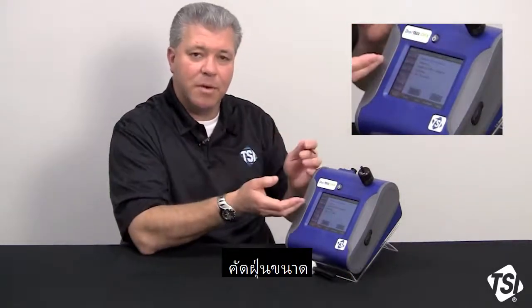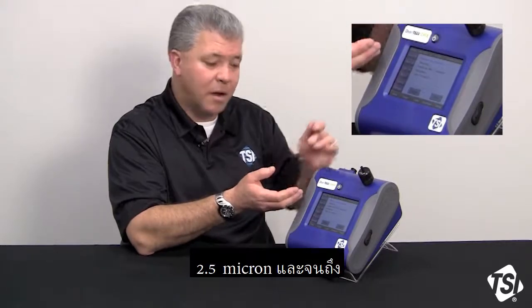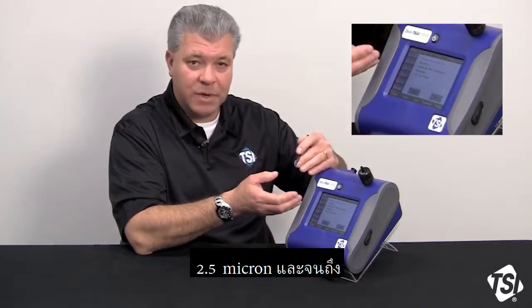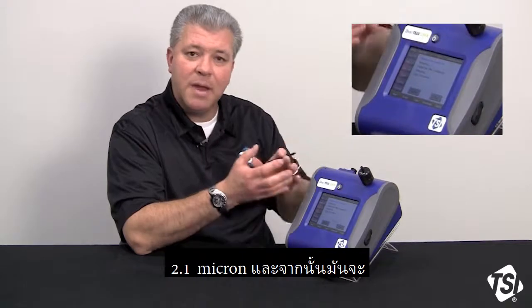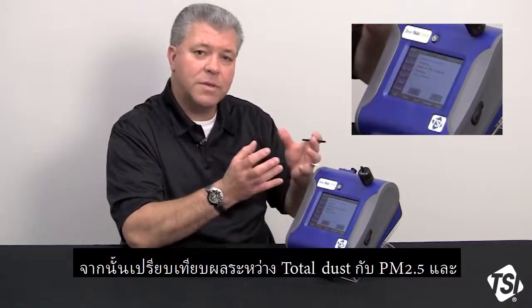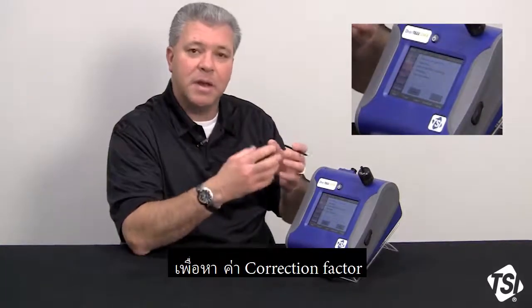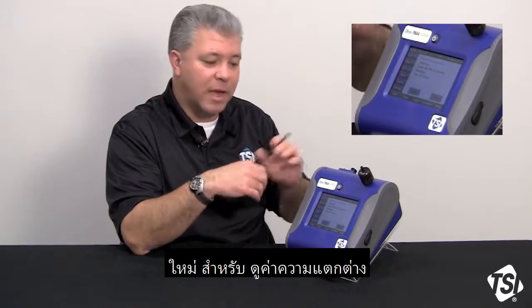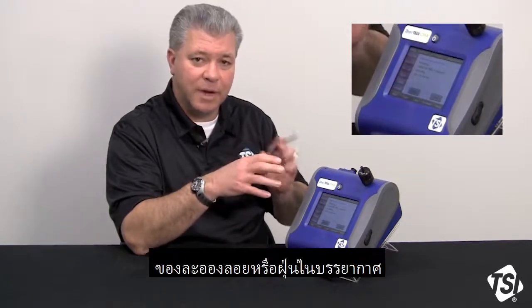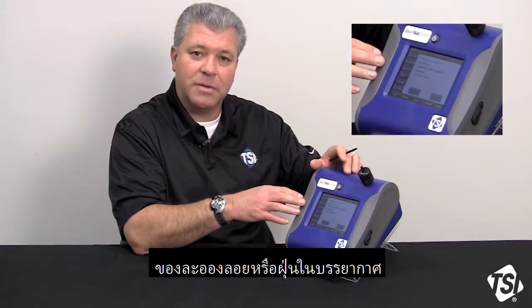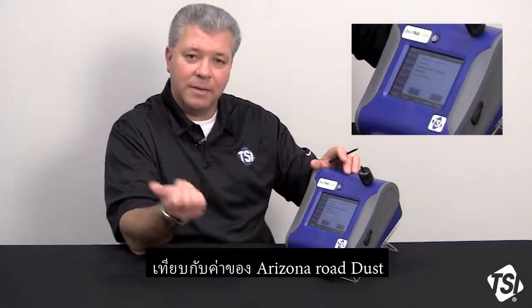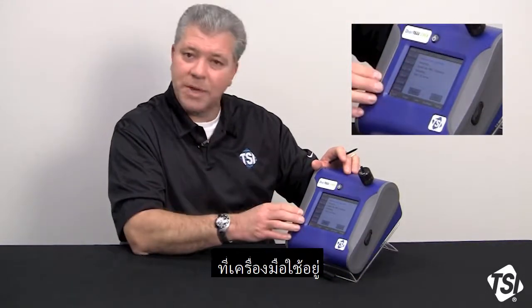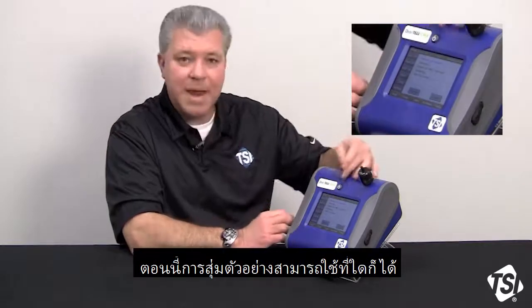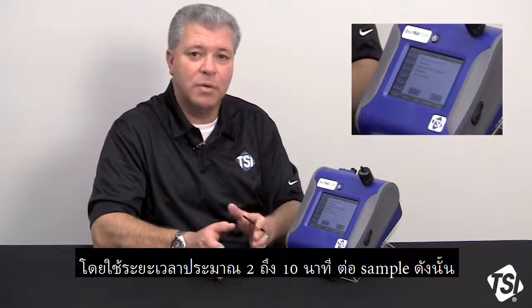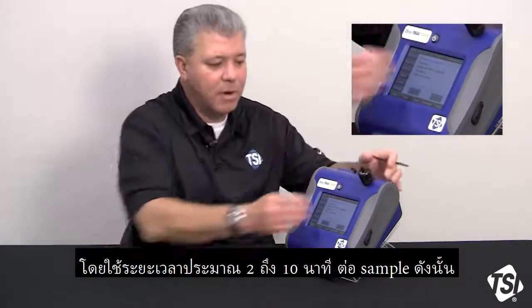It's going to take another representative sample of 2.5 and less aerosol down to 0.1 microns, and then it's going to compare the total versus the PM 2.5, and it's going to come up with a correction factor, looking at any size distribution differences between the ambient aerosol you're measuring and the Arizona road dust that the instrument was calibrated to. Now, this sampling can take anywhere from 2 to 10 minutes per sample.